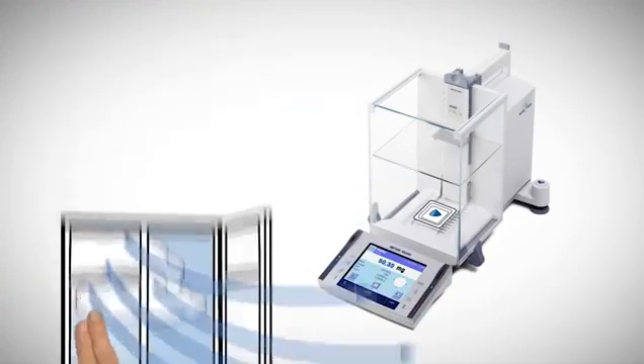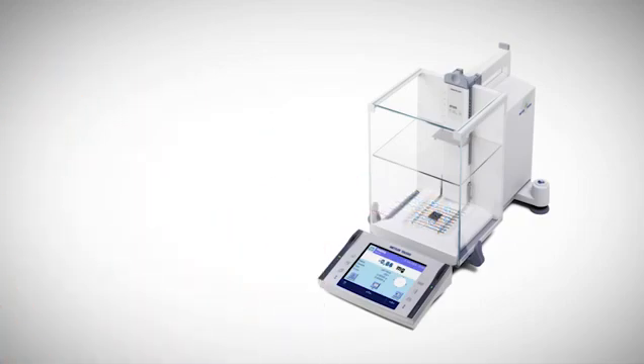USP 1251 provides practical recommendations for the qualification and operation of balances. Among others, it describes several environmental factors that can influence the performance of a balance. For example, air currents, temperature variations, vibrations, electrostatics and many more.